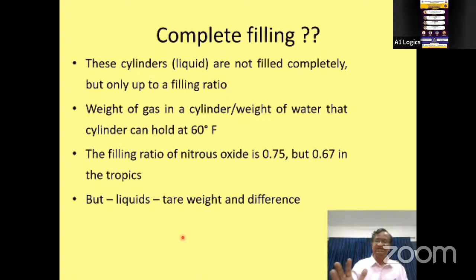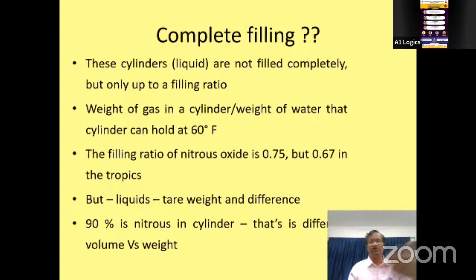These cylinders are not filled completely, but only to a filling ratio. The weight of the gas in a cylinder divided by the weight of the water that the cylinder can hold is the filling ratio. The filling ratio of nitrous oxide is 0.75, and 0.67 in the tropics. So it is around 0.7, 0.67 for nitrous oxide. This is liquid nitrous oxide. Tare weight is the empty cylinder weight. Subtract the empty cylinder weight from the total weight to find the difference, which is the weight of the gas it contains. Yes, we will leave it because it is related to oxygen cylinders.